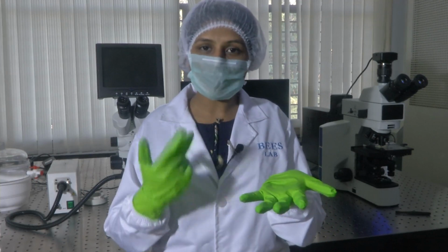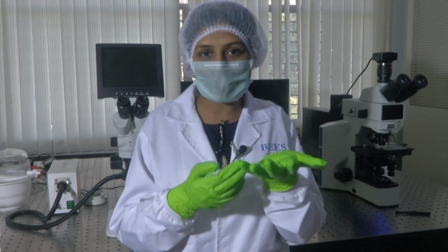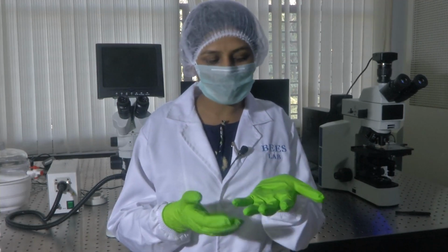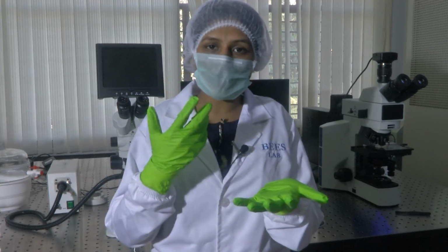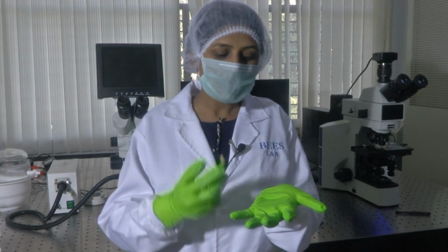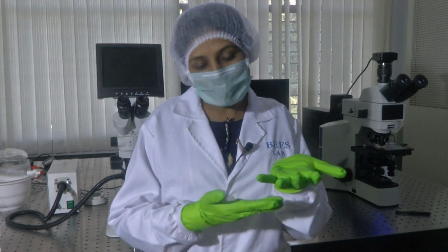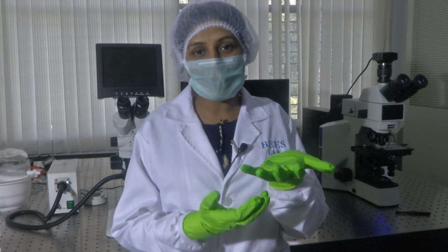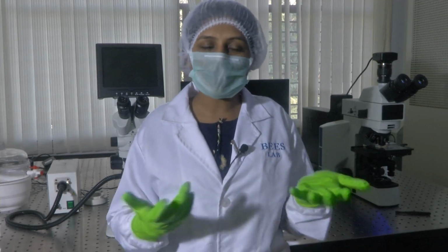When you want to understand the type of microscope, you should understand the features. When we have these petri dishes, it is always understood that the cells have a tendency to settle at the bottom of the petri dish, and they are in a buffered solution which is highly turbid. In microscopy, you shine light, or use any other mechanism, but there would be a lot of interference due to the turbid medium. So you need to look at them from the bottom where the cells are, where you have a better focus and can better study the medium from beneath the petri dish. So you need to understand the microscopy technique where the objective lens could be at the bottom and then you shine light from the top.